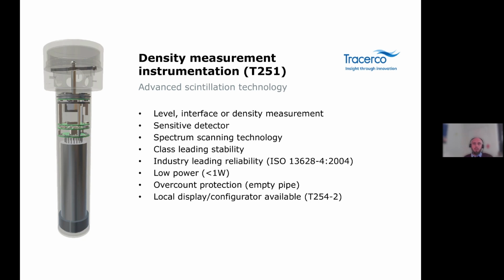The advanced signal processing of the density measurement system provides a base for enhanced discrimination to offer protection against the higher ionizing radiation fields that may be encountered, such as radiography. It employs dynamic compensation that accurately compensates for the effect of the ambient temperature variations and aging in the scintillator. This is achieved by tracking and maintaining the position of the radioisotope photopeak through varying the gain of the system.